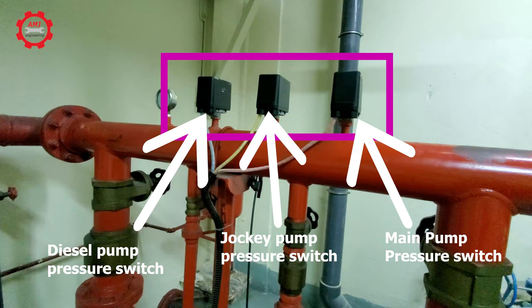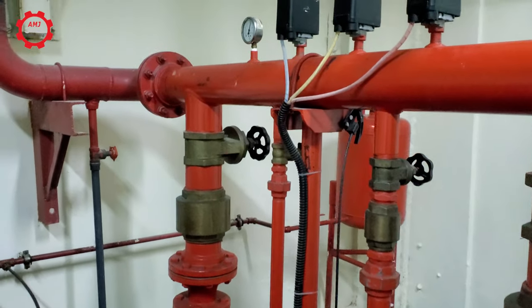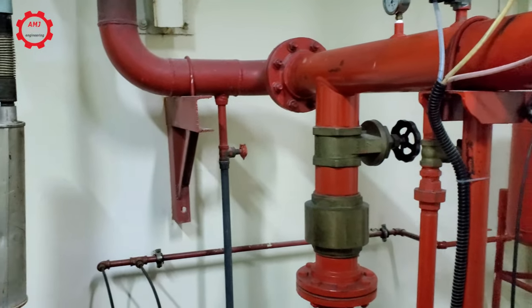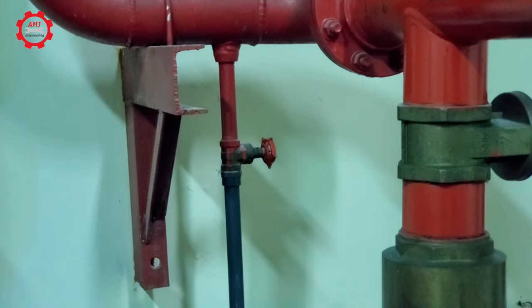These settings are provided here, so the jockey pump will start and stop automatically based on the system pressure. Let's do the experiment here. I'll open the drain test valve on the discharge line to reduce the system pressure.